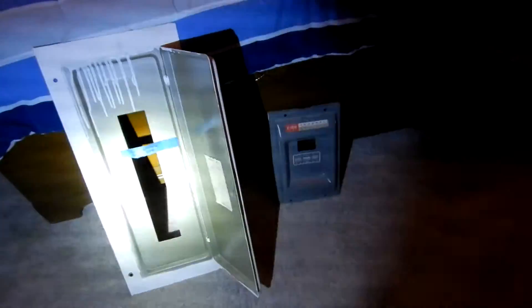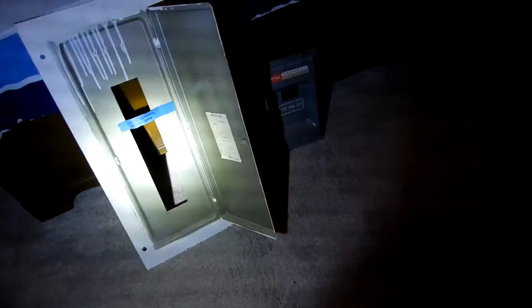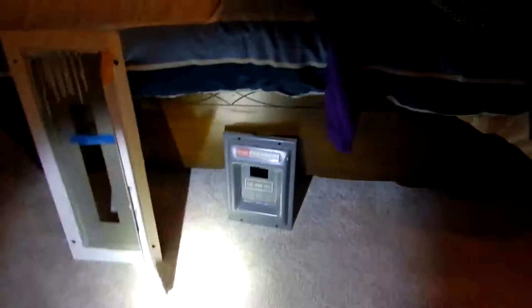Remember in the last episode we left off at - this is a Magnetrip Zinsco breaker box, this is a Federal Pacific breaker box. The home inspector doesn't like these boxes. He considers them fire safety hazards. Electric service panels are not supposed to be located in the closet.